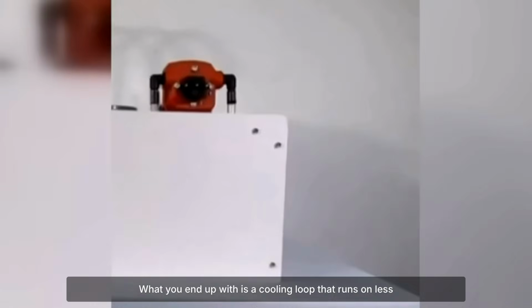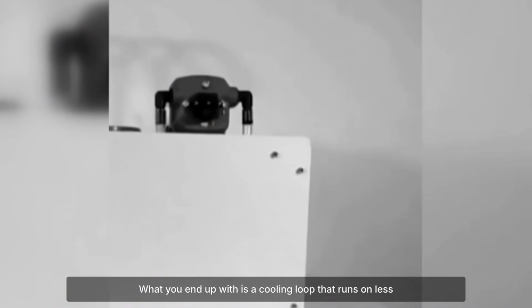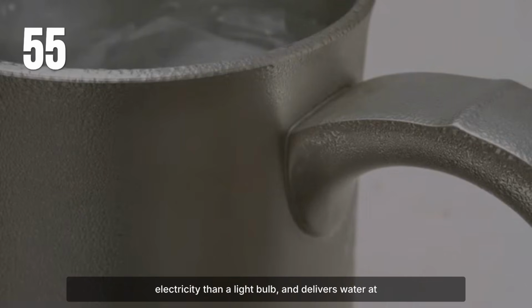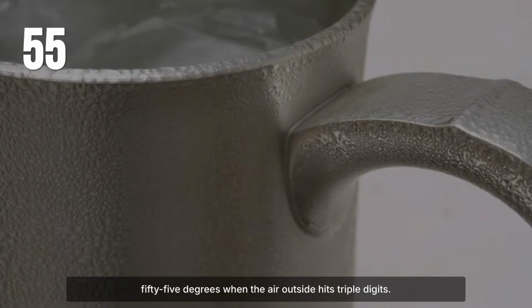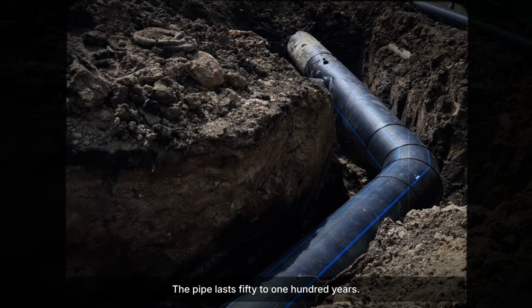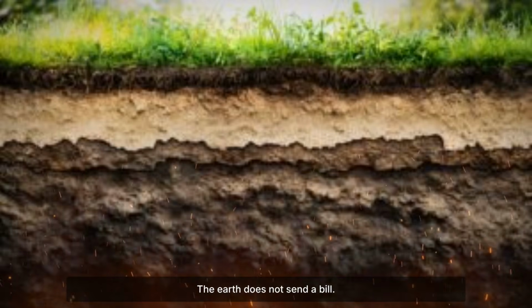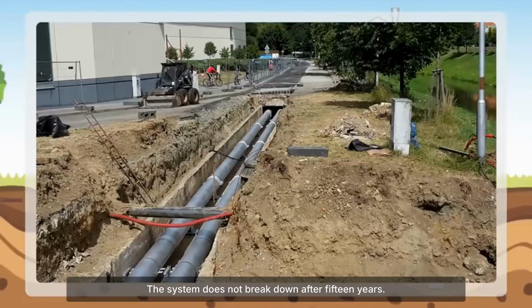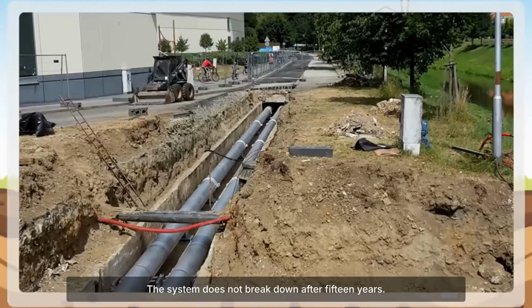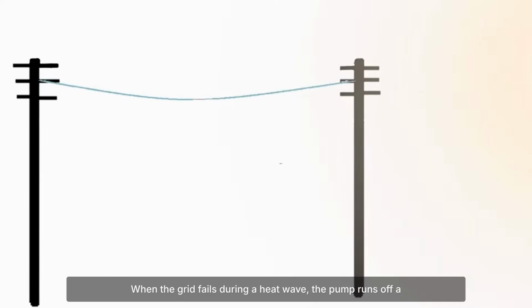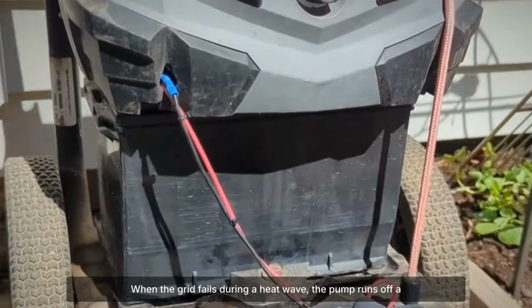What you end up with is a cooling loop that runs on less electricity than a light bulb and delivers water at 55 degrees when the air outside hits triple digits. The pipe lasts 50 to 100 years. The earth does not send a bill. The system does not break down after 15 years. When the grid fails during a heat wave, the pump runs off a car battery.